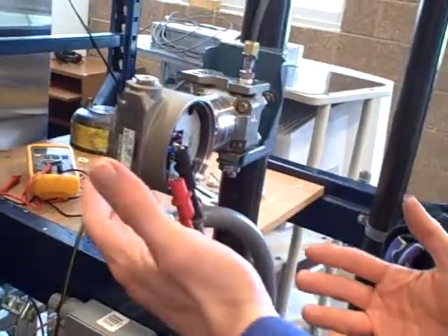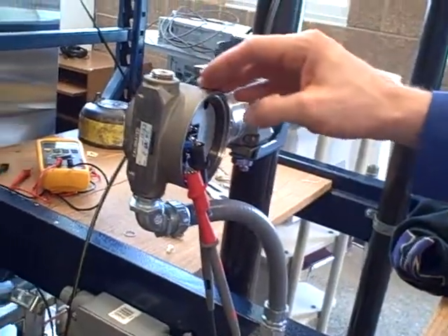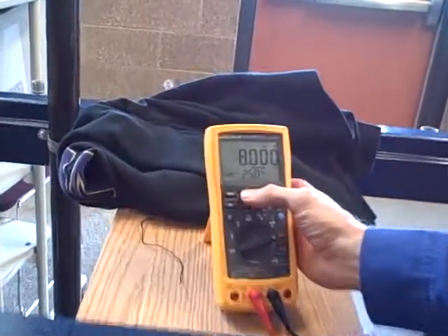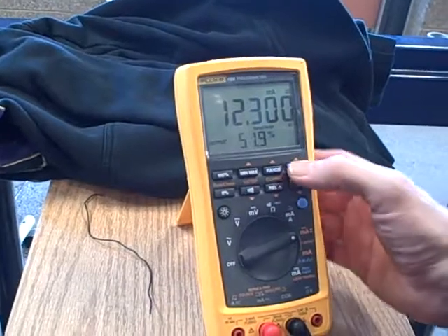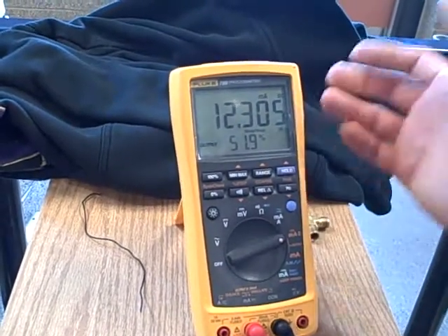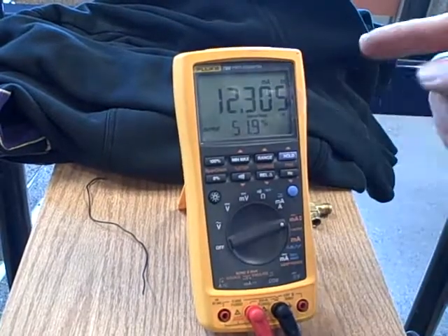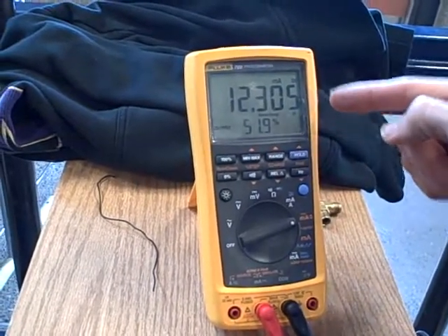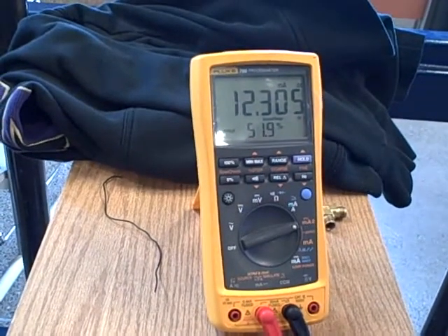It's relying on the power source, the loop power source, to provide loop power, but now instead of the transmitter circuitry regulating current, this is regulating current. So I get to tell it, do I want 8 milliamps in the circuit? Do I want 12? Do I want 12.3? Do I want 12.305? I can dial it up and down just like I did before, but this time, instead of this supplying the electrical energy, it's merely regulating the current the same way a two-wire loop power transmitter would regulate the current.